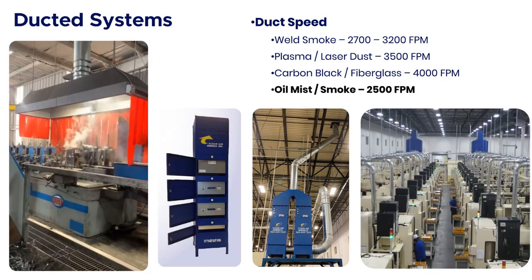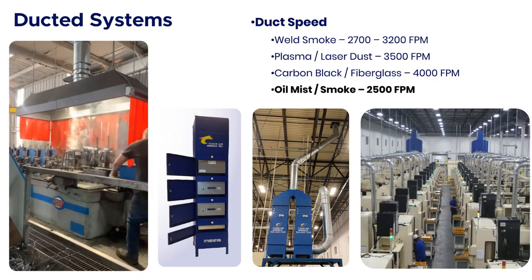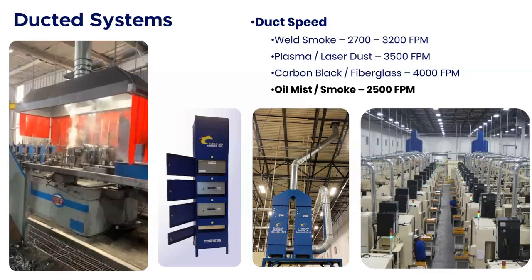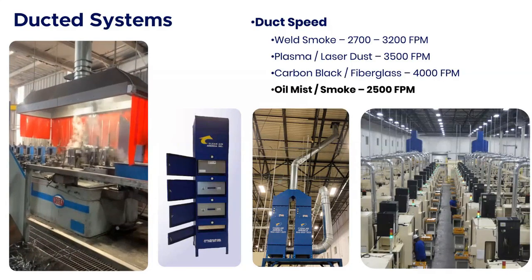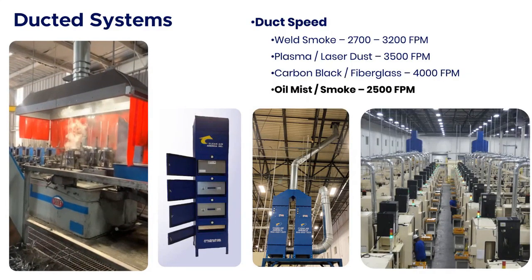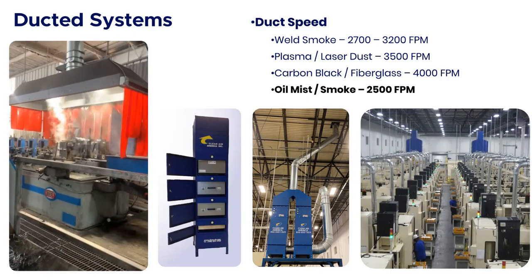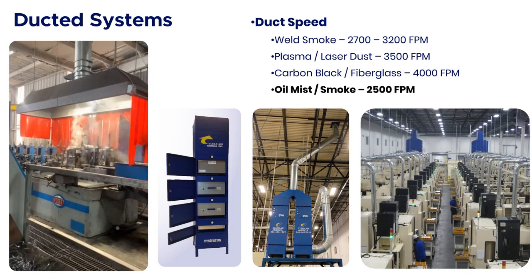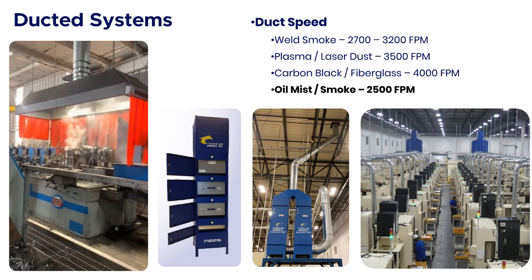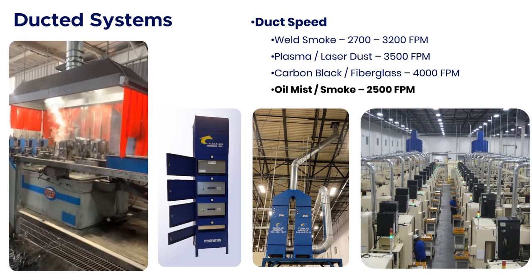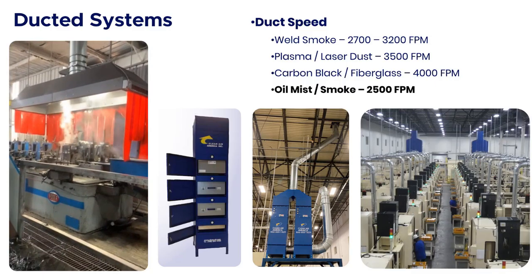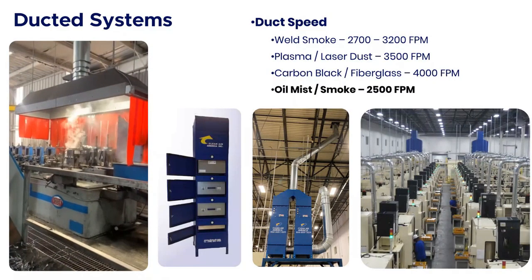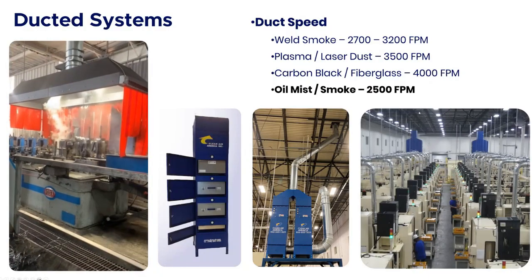That thing's about the size of a pallet, and it's about 16 foot tall. But that is our workhorse. That's when you have the really nasty applications, like a tube mill that sits there and runs 12 hours a day, 6 days a week. I've got one of those not too far from our plant that I've been able to keep a good eye on, and we're over 2.5 years on the filter life so far, and they still don't need to change the filters.